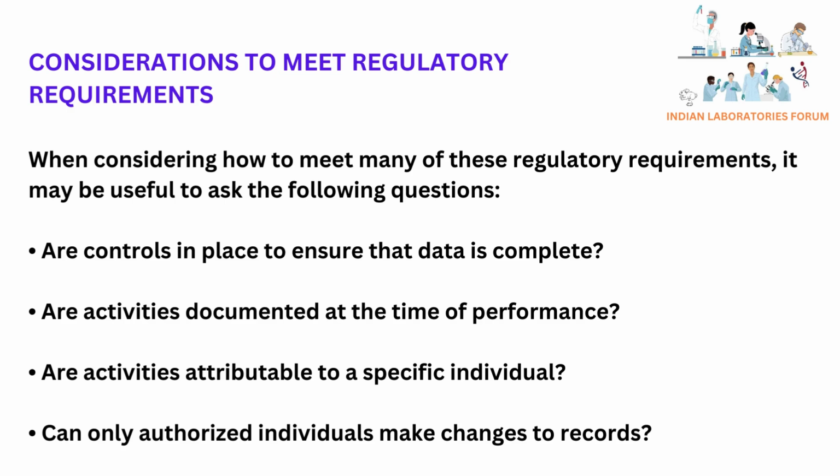Considerations to meet the regulatory requirements. These are the minimum requirements to consider for meeting the requirements of regulatory bodies for data integrity. Are controls in place to ensure that data is complete? It means control measures are in place such as review mechanism, audit trails, access privileges, etc. Are activities documented at the time of performance? Are activities attributable to a specific individual? Can only authorized individuals make changes to records, such as user privileges and authorization for making the changes?